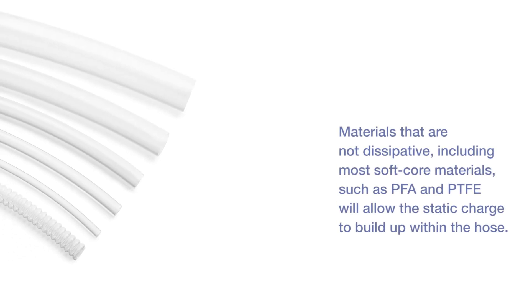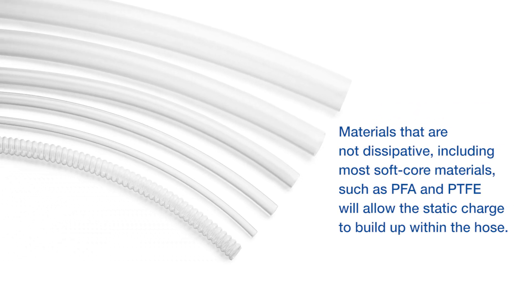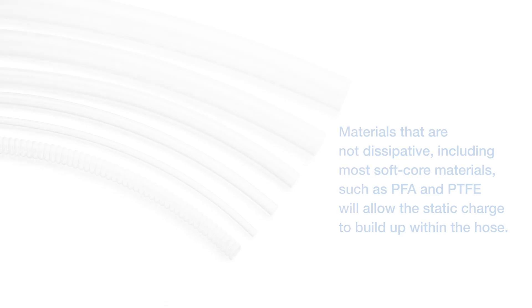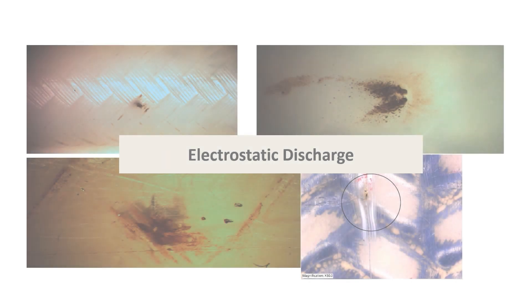Materials that are not dissipative, including most soft core materials such as PFA and PTFE, will allow the static charge to build up within the hose. This kind of buildup can cause a tiny hole in the hose to develop, resulting in a hard-to-detect system fluid leak and providing a path for any pent-up static electricity to jump to the closest conductive material. Any size hole creates a hazard in environments using toxic or combustible gases or liquids.